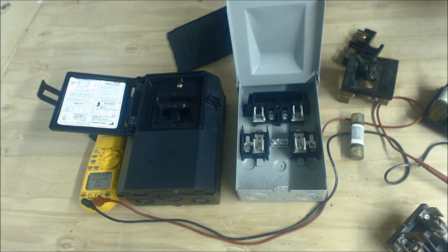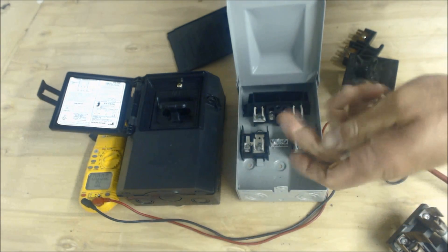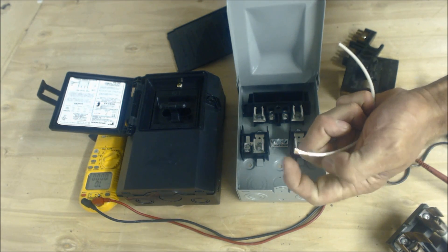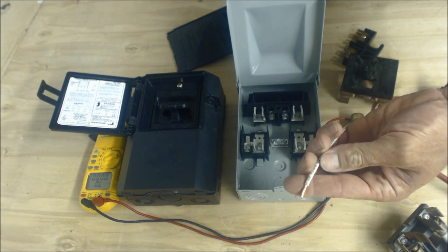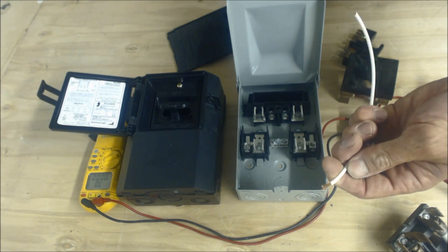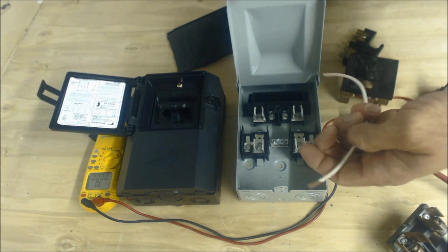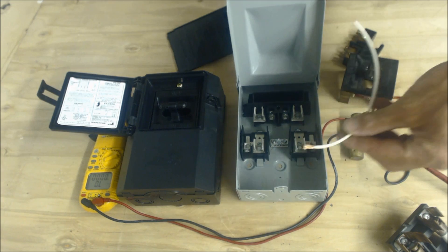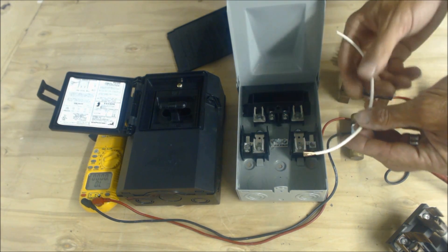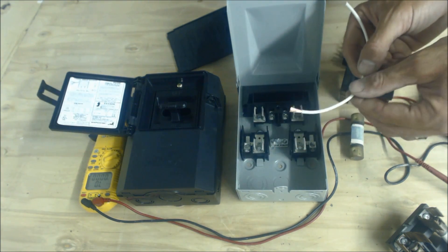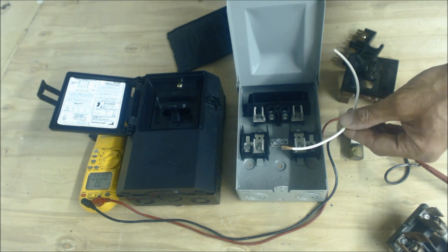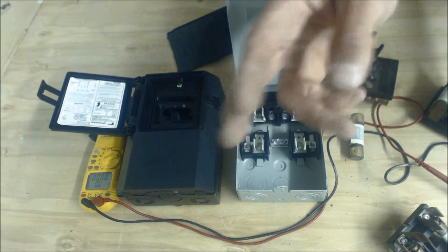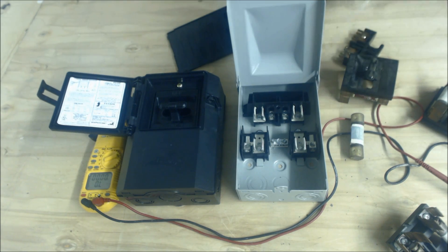Make sure that you, in your whip, you have the proper gauge wire. And that's the THHN or THWN, and you're putting that in your whip. So make sure that this wire gauge size matches or exceeds the amperage rating of your fuses or your breaker.